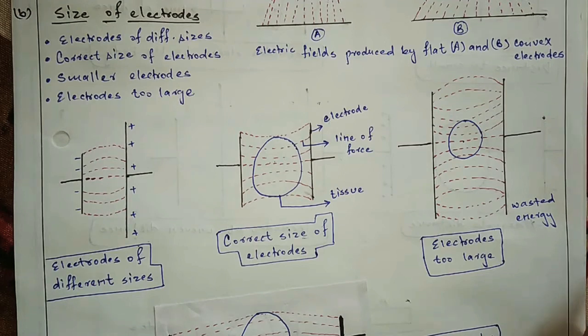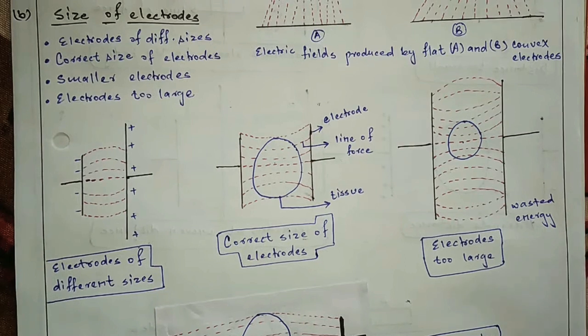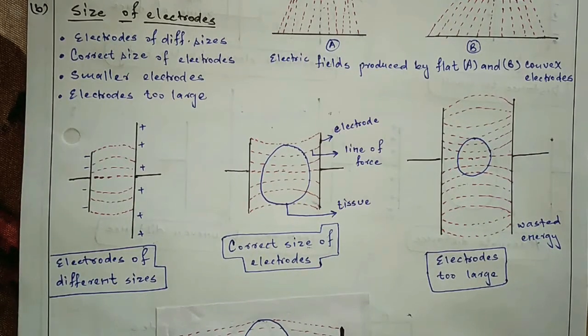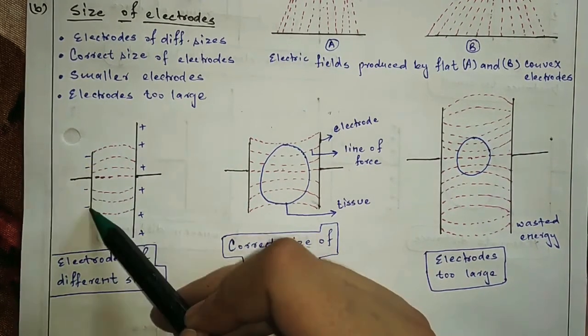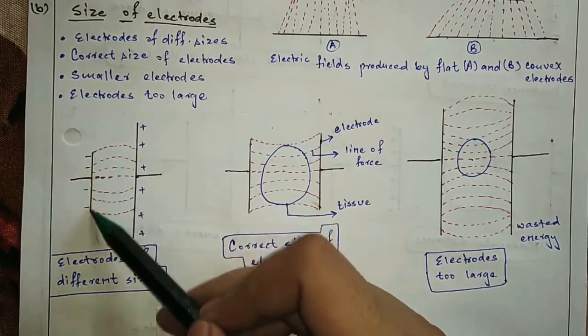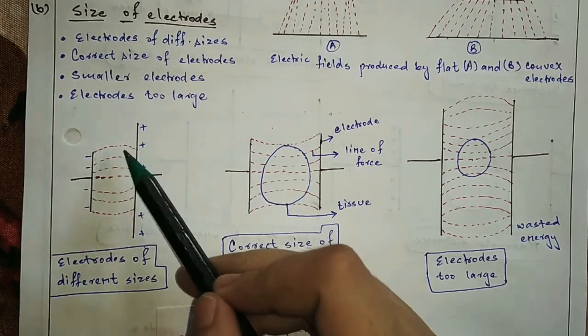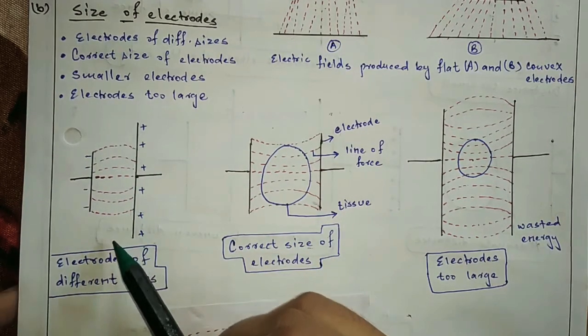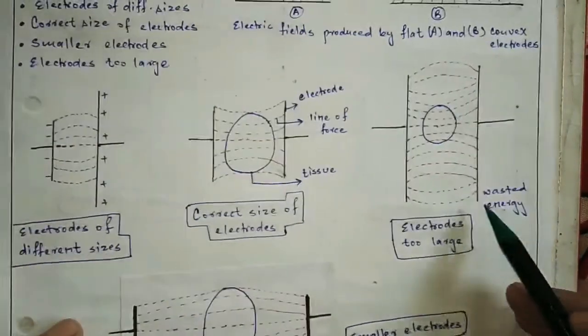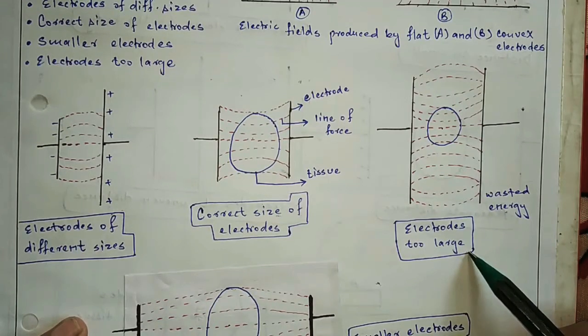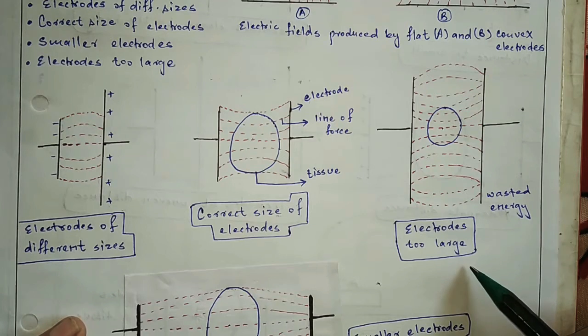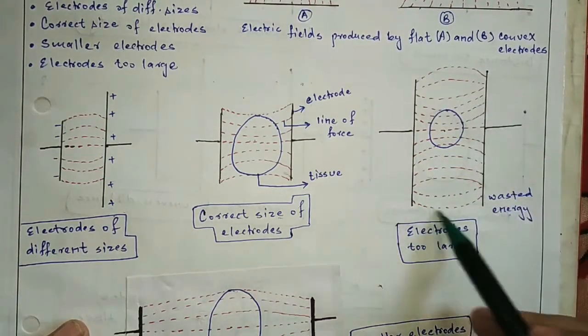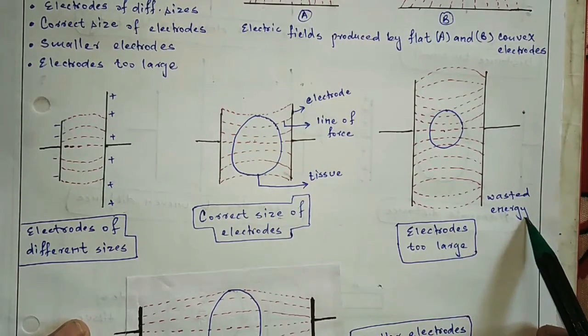The electrode should be bigger than the body part because the electric field spreads at the edges, so the body part should be in the center. However, the electrode should not be too large — if it is too large, the electric field disperses from the edges and this is a waste of energy, so it is not advisable.